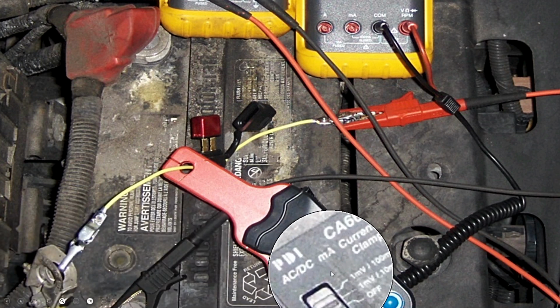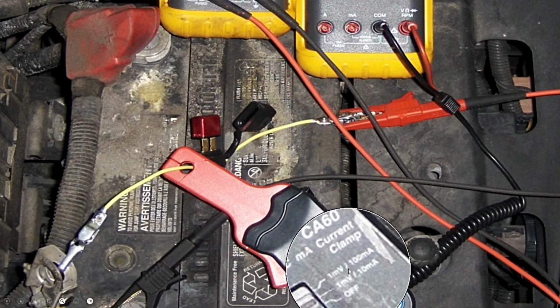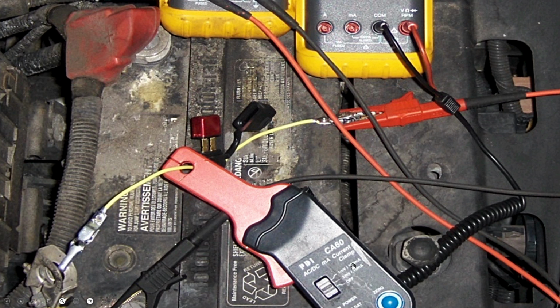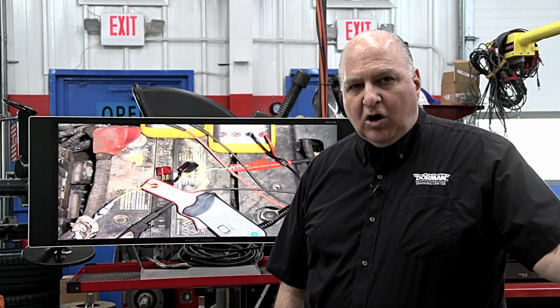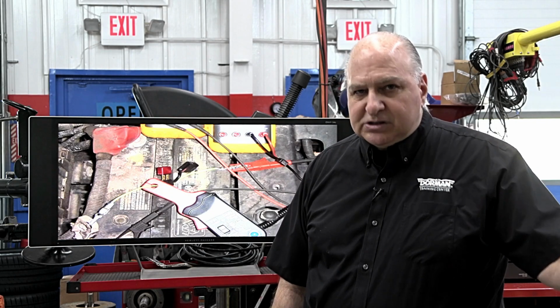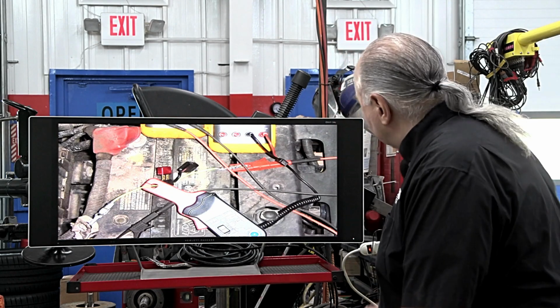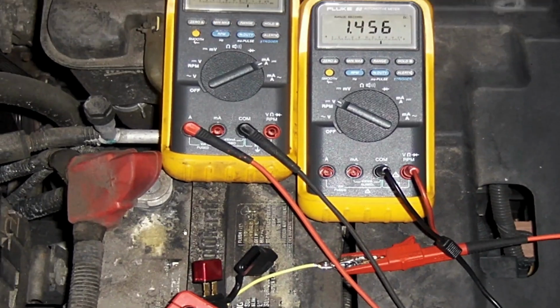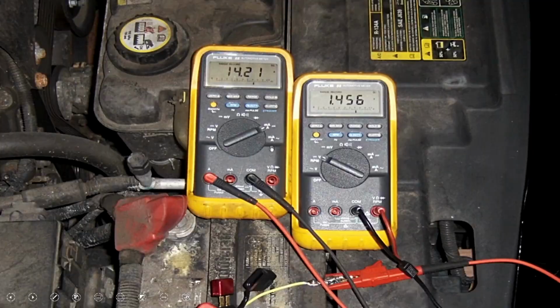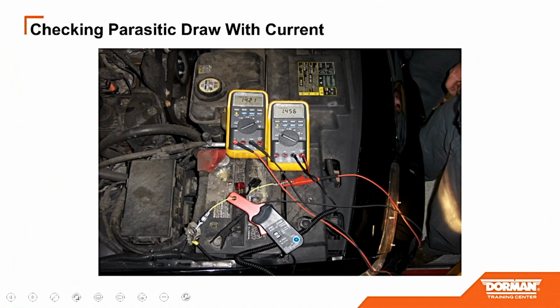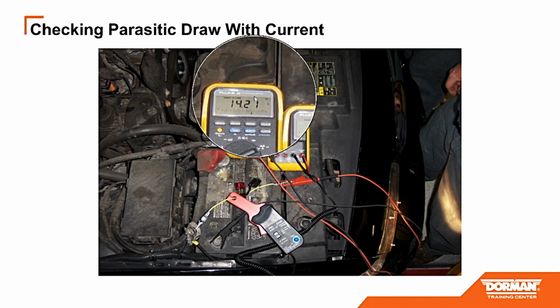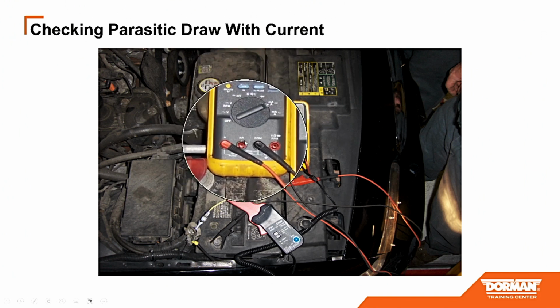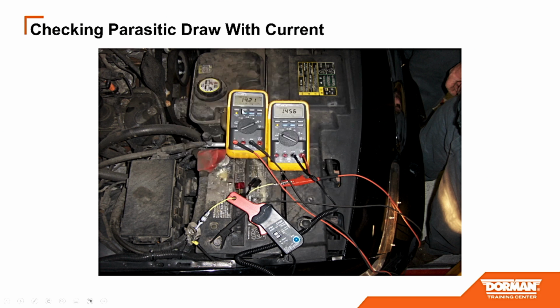You're going to be on a scale where 1 millivolt equals 10 milliamps, which really means every 100 millivolts equals 1 amp. So every 3 digits on the display equals an amp. Let's go over that in a second. So this vehicle is pulling 14 amps, 210 milliamps, as you can see on the meter that's directly hooked up.